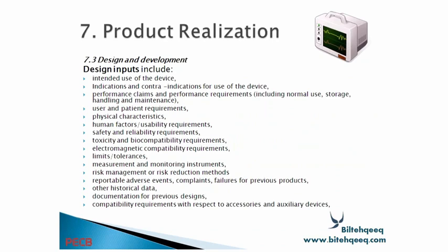And design input includes intended use of the device, indications and contraindications for use of the device, performance claims and performance requirements including normal use, storage, handling and maintenance, user and patient requirements, physical characteristics, human factors, usability requirements, safety and reliability requirements, toxicity and biocompatibility requirements, electromagnetic compatibility requirements, limits, tolerances, measurements and monitoring instruments, risk management or risk reduction methods, reportable adverse events, complaints, failures for previous products, other historical data, documentation for previous design, compatibility requirements with respect to accessories and auxiliary devices.